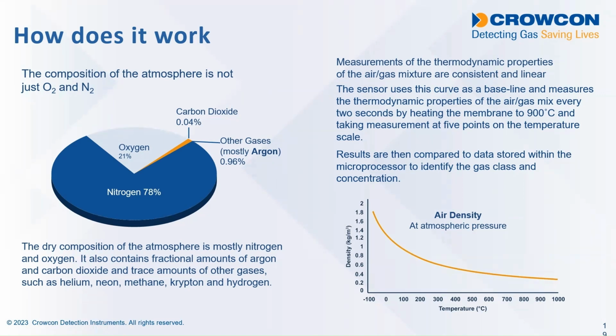So you see a pie chart there. The composition of the air that we're breathing is mainly nitrogen, about 78%. It's about 20.9% oxygen. There's about 400 parts per million carbon dioxide. And then there are some other gases making up the remainder, the most notable of which is argon at just under 1%. So the sensor takes that air mix as stable as a norm, and it's measuring changes in the thermodynamic properties of the air mixture which it's exposed to.